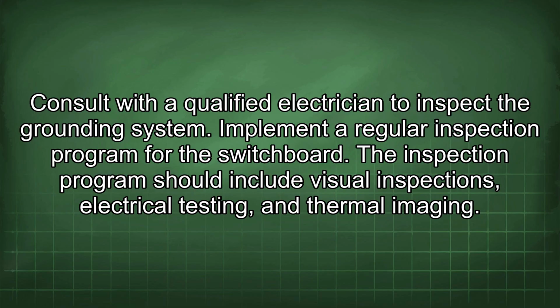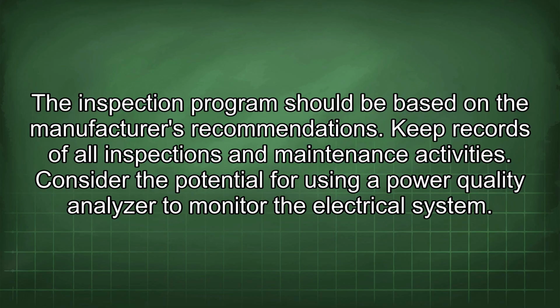Implement a regular inspection program for the switchboard. The inspection program should include visual inspections, electrical testing, and thermal imaging. The inspection program should be based on the manufacturer's recommendations. Keep records of all inspections and maintenance activities.